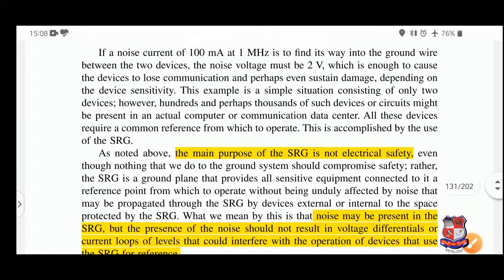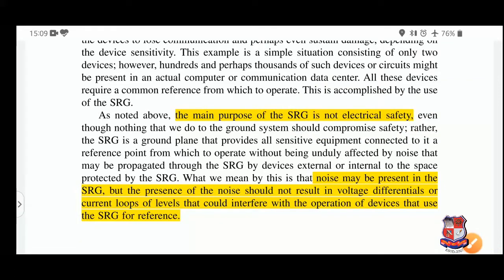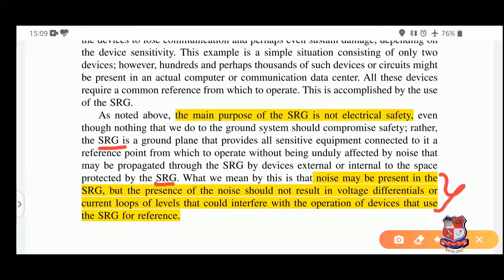The aim of SRG is to minimize noise by providing a lower impedance reference — the ground path. The main purpose of SRG is not electrical safety; that is already handled by earthing or separate grounding. Here we are talking about sensitive equipment. The SRG is a ground plane that provides all sensitive equipment connected to it a reference point from which to operate without being unduly affected by noise propagated through the SRG. The noise may be present in the SRG, but it should not result in a voltage differential or current loops that could interfere with device operation.